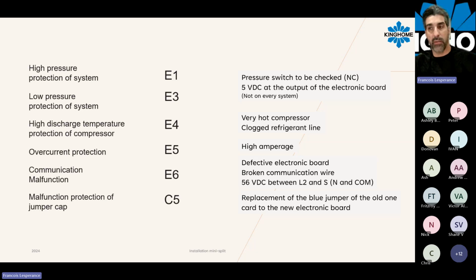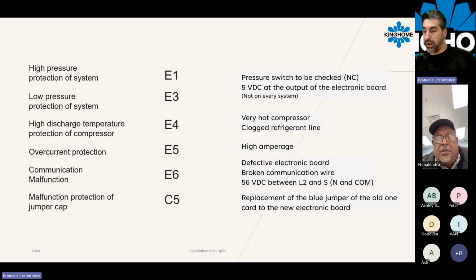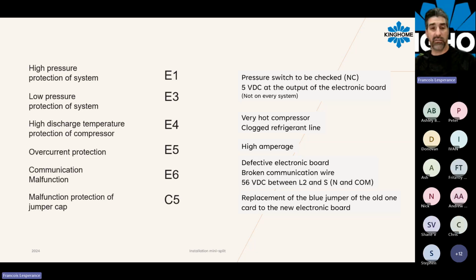E6 is the most common communication malfunction error. That's the one we just told you to look at, the terminal 1 and terminal 2. So you are looking for 56-volt DC out on those terminals at the outdoor unit. If you don't have the 56-volt DC steady on the terminal 1 and 2, that's just because your outdoor board is not communicating.